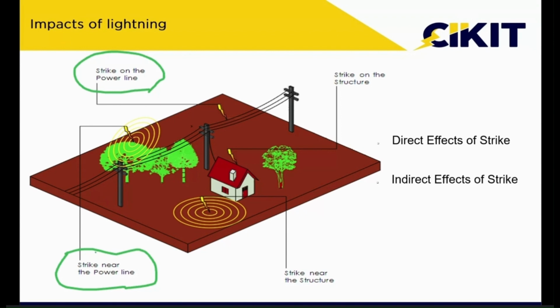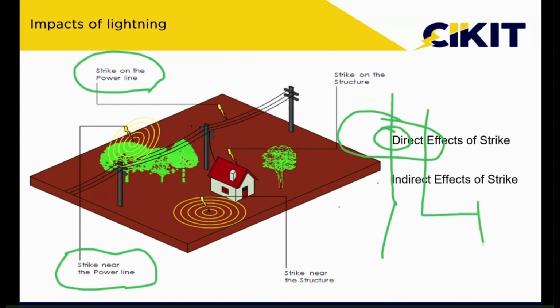That is the reason that, even if you install an external lightning protection system, the electronic equipment inside the house may fail. For example, if I have a down conductor and a current is flowing through it, a magnetic field will be produced surrounding this conductor. The magnetic field will be in the form of concentric circles, and if I have any power line or data line near it, the magnetic field links with that conductor, and I am connecting that conductor to an equipment. Because of the surges induced on this power line or data line, the electronic equipment may fail. Here there is no direct physical connection between these two conductors, but because of magnetic field coupling, the surges get induced and result in failure of electronic equipment.